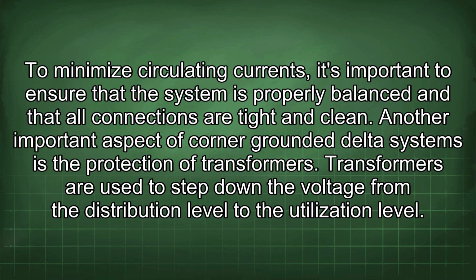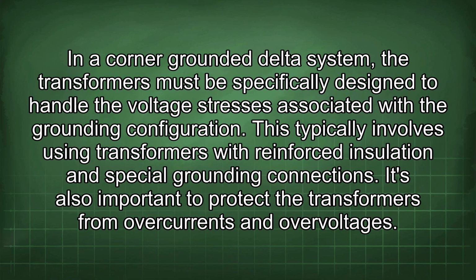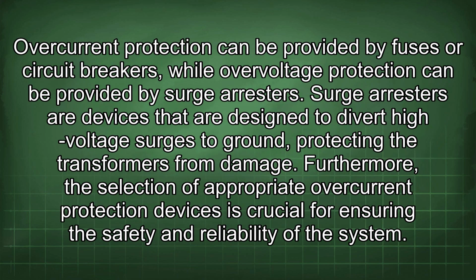are tight and clean. Another important aspect of corner-grounded delta systems is the protection of transformers. Transformers are used to step down the voltage from the distribution level to the utilization level. In a corner-grounded delta system, the transformers must be specifically designed to handle the voltage stresses associated with the grounding configuration. This typically involves using transformers with reinforced insulation and special grounding connections. It's also important to protect the transformers from overcurrents and overvoltages. Overcurrent protection can be provided by fuses or circuit breakers, while overvoltage protection can be provided by surge arresters. Surge arresters are devices that are designed to divert high-voltage surges to ground, protecting the transformers from damage.